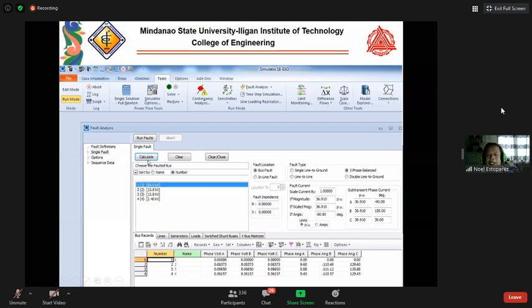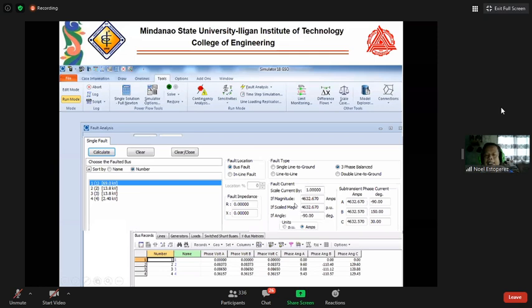So when we calculate this, calculating the fault here will give us, in terms of the magnitude of our fault, very similar to what we have done manually, 4.6 kiloamperes. So this matches our manual computation.